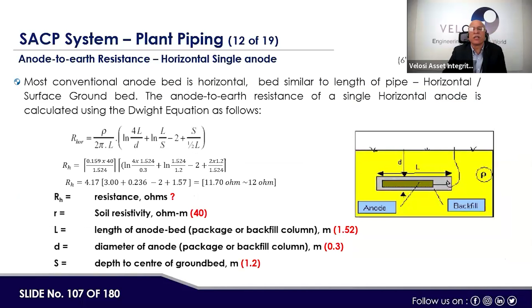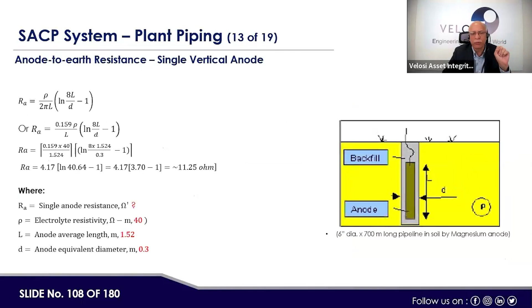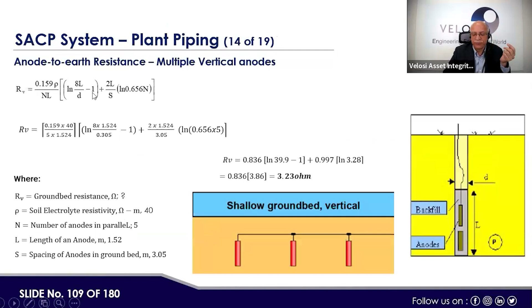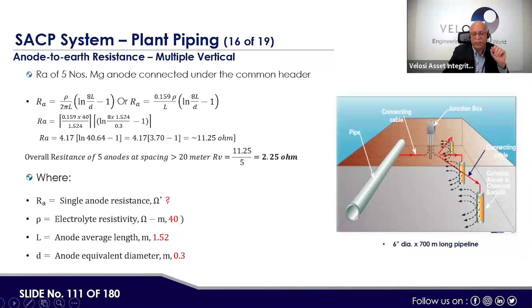Second, for the anode-to-earth resistance of a single vertical anode, this is the formula and we can calculate it. I'm just showing you because there is no time to go through all the detail. It takes a lot of time to go through this process. Then the anode-to-earth resistance for multiple vertical anodes, the equation is there. The same calculation continues, and here the multiple vertical anode calculation is completed.